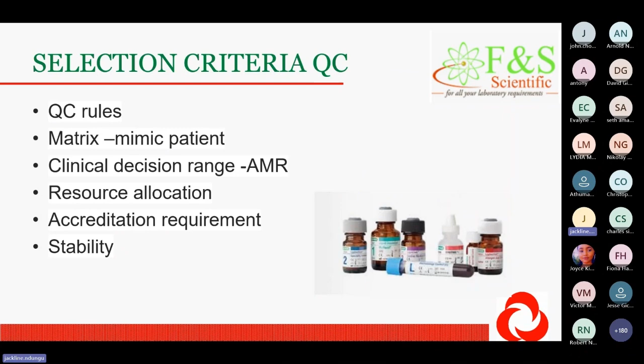What are some of the key elements of quality assurance? And this slide was supposed to appear before the other one. So as I have mentioned about quality control, that was basically internal quality control. So you also need to do some equipment calibrations. I just mentioned a few, but in terms of quality, after you have done calibration, you also need to verify your calibration. What happens to us as an institution is that we have enrolled in CAP and we get that material to do our verification. It is called CVL. CVL is calibration, verification, and linearity.